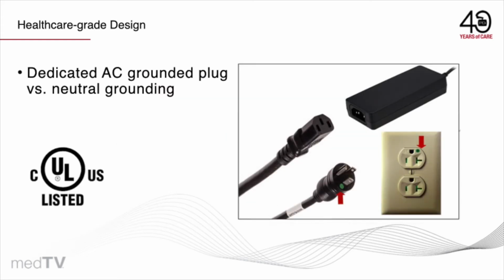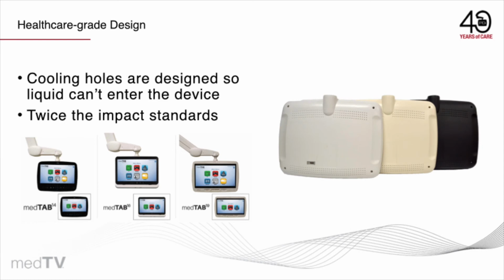AC grounded plug, I mentioned that. There is a healthcare grounding plug. If anybody's seen a receptacle with a green dot in your facilities, those are guaranteed grounded, not just a neutral ground, but a dedicated ground. And the plugs on a UL listed healthcare device must also mate to that. If you purchased a consumer grade product recently, you'll notice one of the plugs is larger and one smaller. That's because they're using the neutral line as a ground, and it can be broken. A dedicated ground is much less likely to be broken. All of the cooling holes in the television designed for healthcare by PDI are angled and ported in a direction where liquid sprayed on it will not ingress or come inside of the television, so you can easily spray it down with a bottle and wipe it clean. Twice the impact standards of a consumer grade set as well.